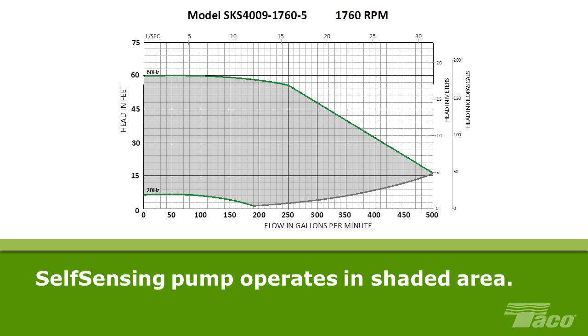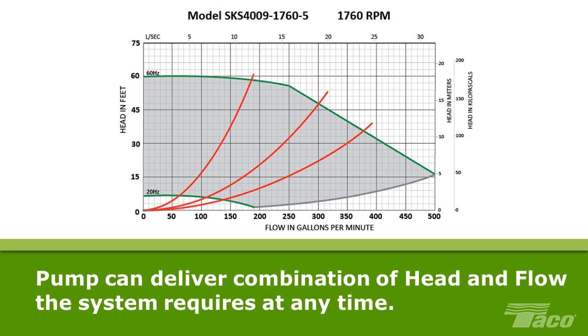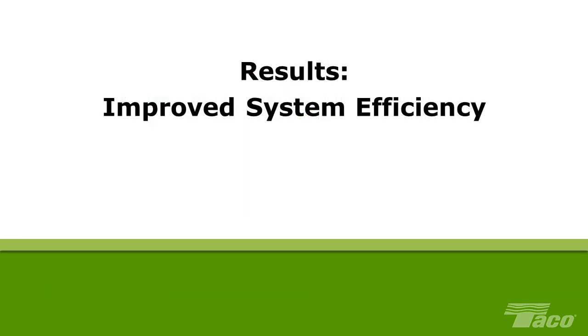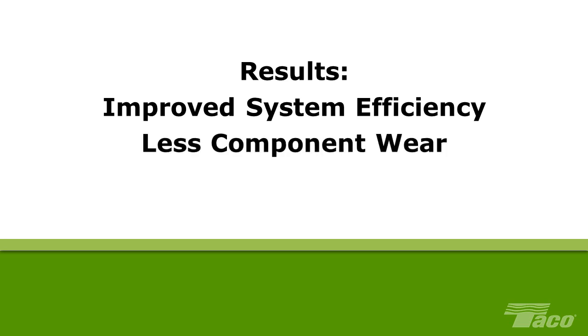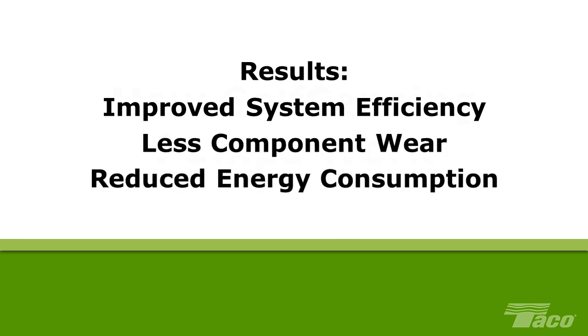Here's the performance curve for the Taco model SKS 4009 self-sensing pump. This pump can operate at any combination of flow and head in the shaded area of the graph. In other words, by varying its speed, the pump can deliver the precise combination of head and flow that the system requires at any given moment. The results are a big improvement in system efficiency, less wear on system components, and reduced energy consumption.